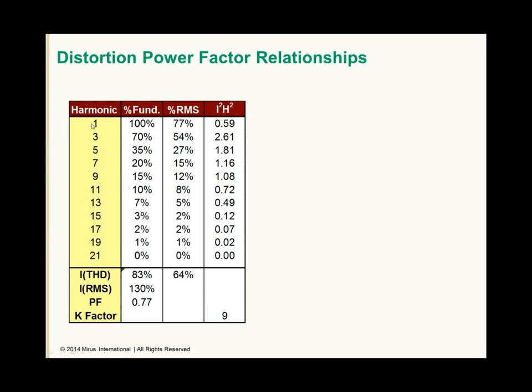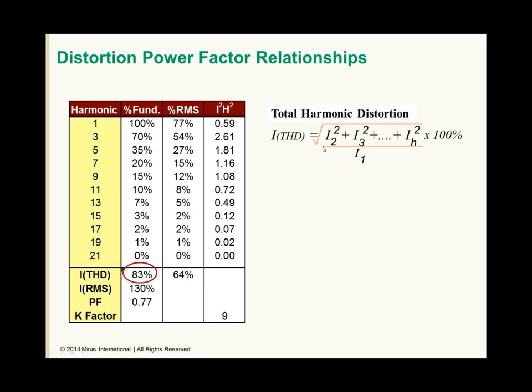It'll always be 100% of the fundamental component by definition. Third harmonic here we're saying is 70% of the 60 hertz or the 50 hertz fundamental component. Fifth harmonic's 35%, seventh is 20, and so on. Our total harmonic distortion, which is represented by the square root of each harmonic squared, and the sum of those, take square root, and then we divide by the fundamental component. That measurement is 83% with this load profile. The same load profile, though presented as a percent of RMS, has the fundamental being 77% of the total RMS. The RMS total here is 130%. 54% third, 27% fifth, for a total THD of 64%.